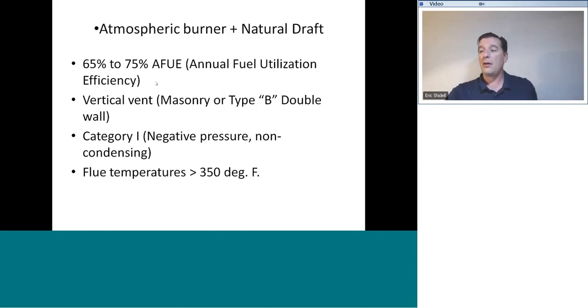It's very important. You may find the vent be a masonry type, or it may be a type B double wall pipe, B vent. Metal asbestos, Hart-Cooley vent pipe, that's that stuff. Masonry vents are kind of going away. They were okay when there was draft diverters on all the appliances, but we're going to start talking about appliances that don't have draft diverters, and for those, we can't use a masonry vent anymore. Be aware, almost all 80% efficient appliances need to have a metal vent pipe. It cannot be vented into a masonry chimney, whether it is a clay liner or not. The way the code works out is that generally is prohibited. Very rarely would you be able to sneak it through.